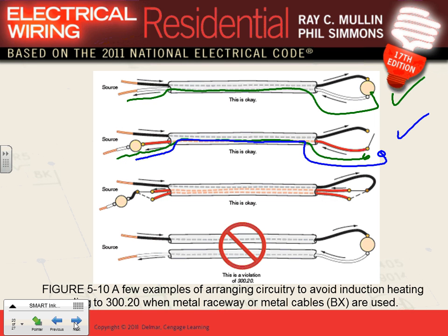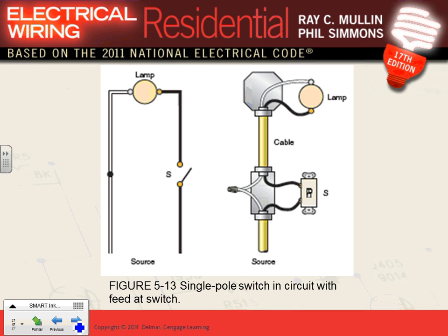This is okay, because we're not feeding a load. We don't bring the neutral with this circuit, and that's okay. We're just switching it. Here's what they don't want you to do. I have 14-2 here. I pulled another 14-2, and I pulled the hot in one 14-2 and the neutral in another. Can I do that? Thumbs up. Good, Chad. Okay, so we got over that.